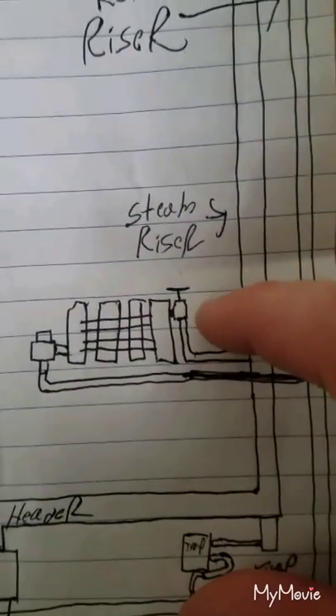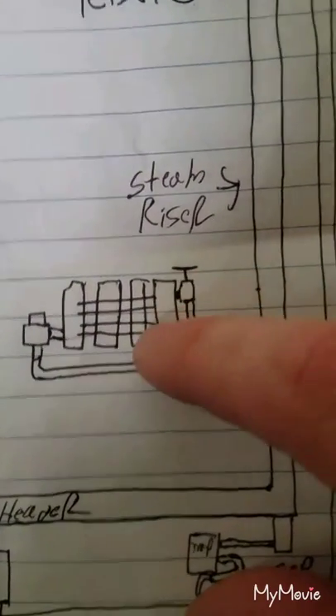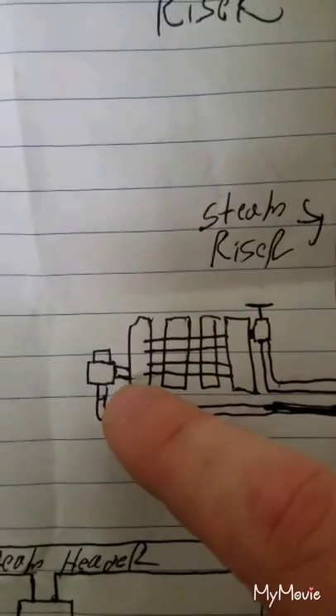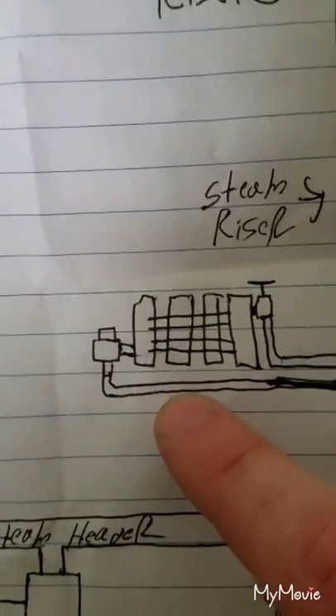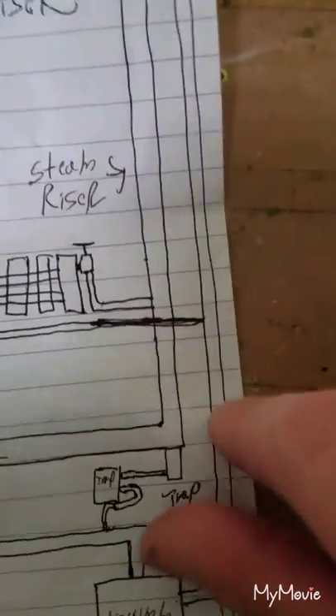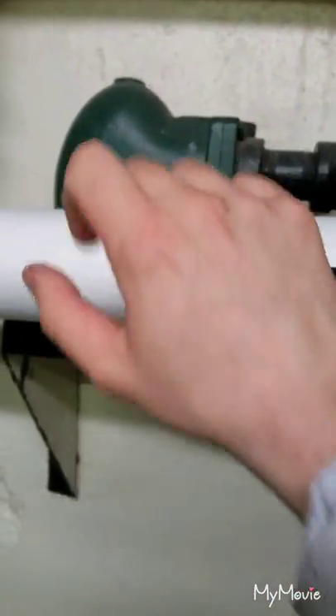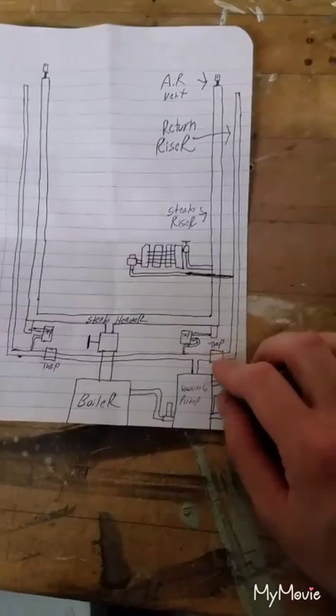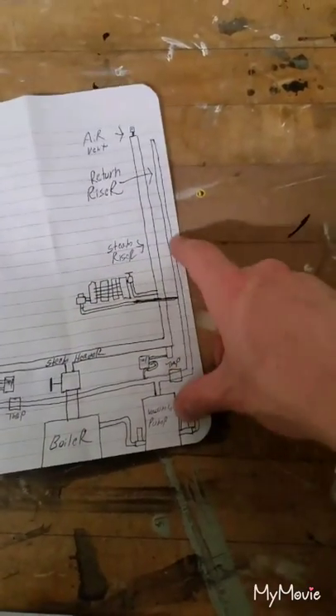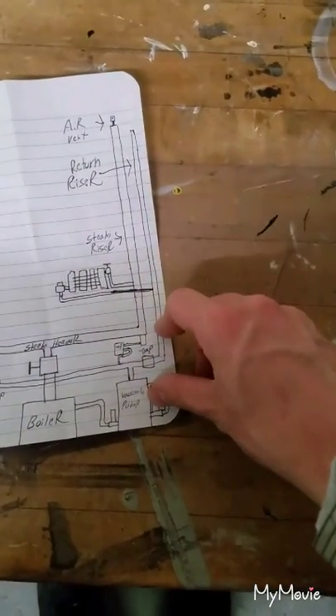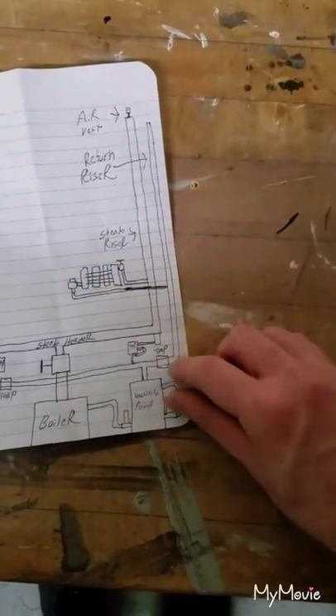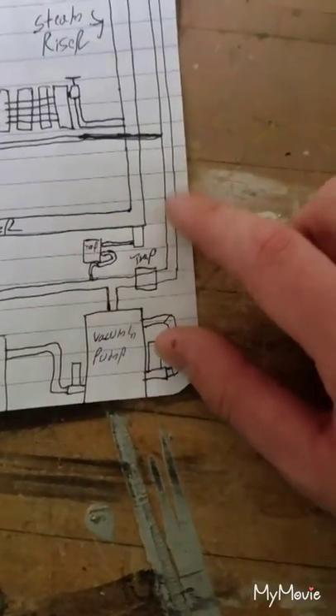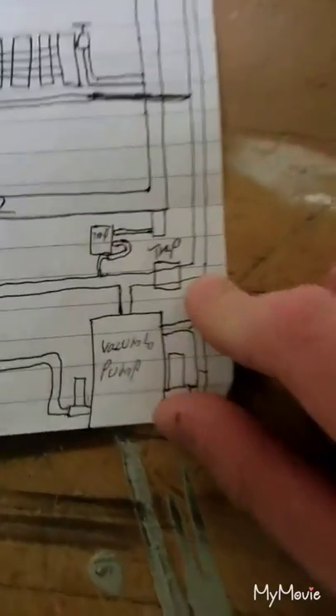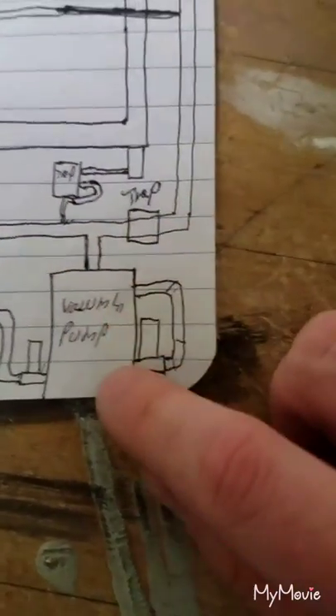The steam branches off into the top of the radiator, works its way down through the sections, into the steam trap, comes back as a condensate into the condensate return riser, which comes all the way down to the basement through a main steam trap, which is a ball swing trap like this. And the reason that it's double trapped, there's a trap here and a trap here, is because in this line you can get flash steam. So that's why it's trapped here, to make sure that if there's still steam in this line, it all comes back as a condensate to the vacuum tank.